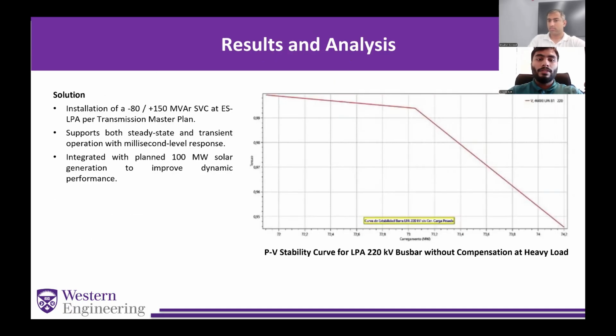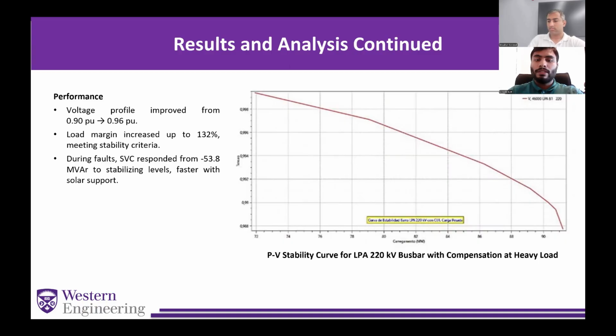Yeah, they installed a 150 MVAR SVC over there, and we can clearly see that the voltage is below 0.95 per unit when the demand is around 74.2 megawatts. Can you go to the next slide, please? So after the installation of the SVC, we can see that even at 80 megawatt demand, the voltage is above 0.99. So it increased the load margin by 132%, and it increased the voltage stability in the system.